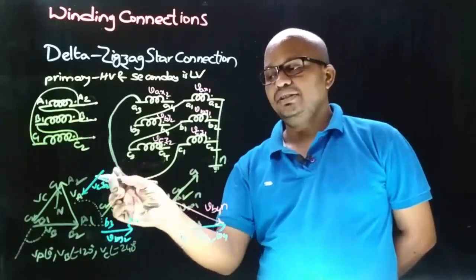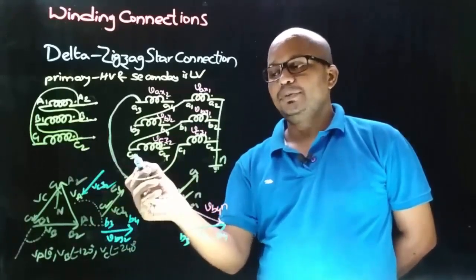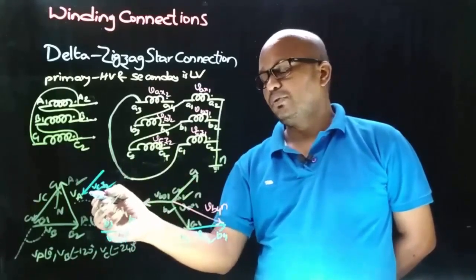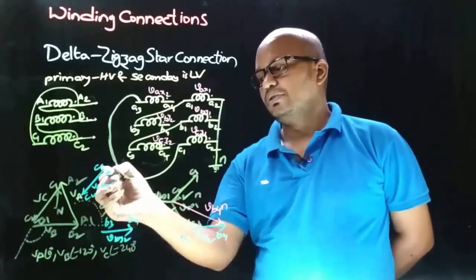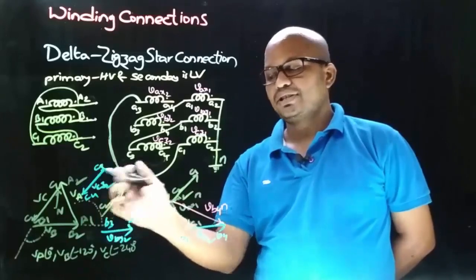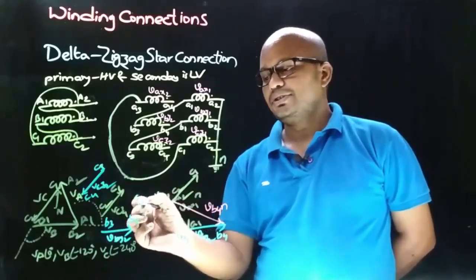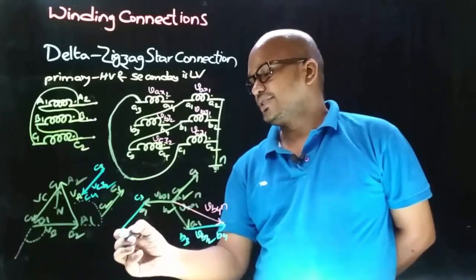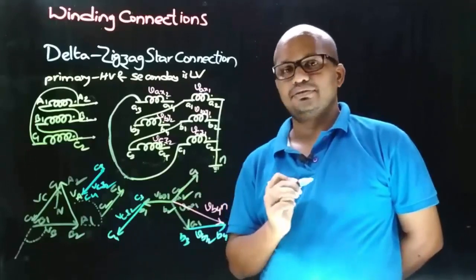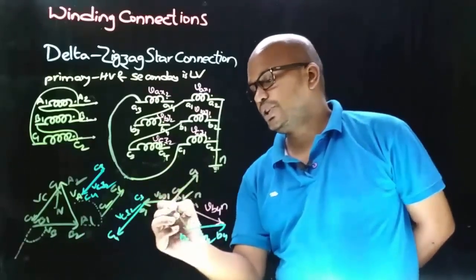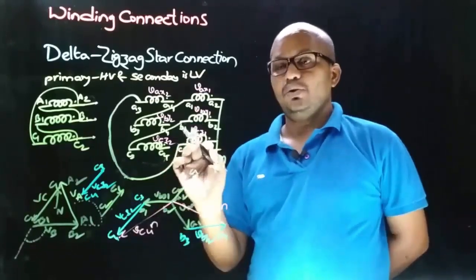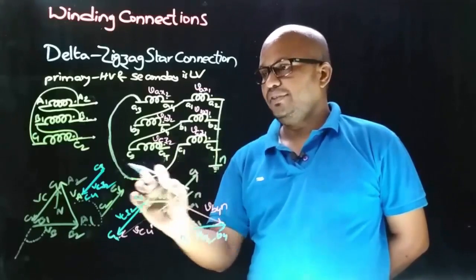And now we need to decide the terminals of the VCZ2 phasor, and the terminals are C3 and C4. As the arrow points towards the connection we took from, therefore the arrow will point towards C4. Therefore the other end is C3. Now draw this VCZ2 phasor such that B1 will have C3. So like this. This is C4 and this is the VCZ2 phasor. Therefore here the resultant voltage is VC4N.